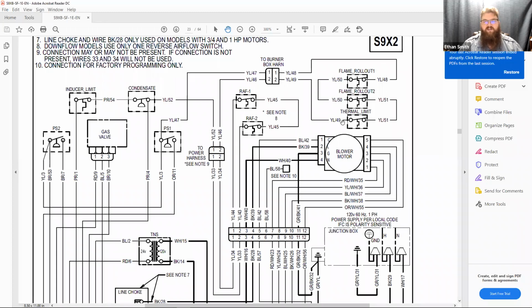Now, if these are all closed here, guys, so we've got 2 flame rollouts and a thermal limit, what should my voltage be between these 2 terminals? 0. Should be 0, because I'm just checking for closed switches, which are 0 voltage drop. Now, if we were to measure from one of these terminals to ground, what would we see? 24, something like that. Yeah, we should see our control voltage there. So 24 volts in this case.